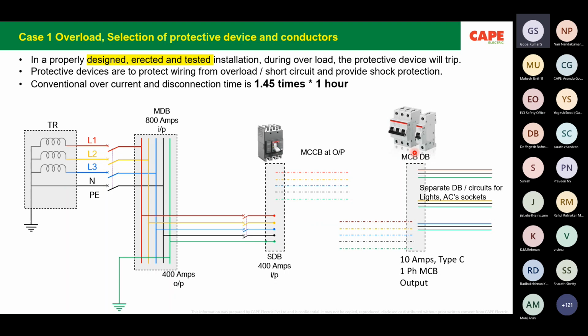In this subject, most of the time what we find is, please note that the protective devices are to protect the circuit, the wiring. Sometimes it is not to protect the equipment, it is to protect the wiring. Equipment will have its own protective device inside. This is the concept. For example, a motor doesn't have any protective device inside, so we are supposed to go for a motor starter, which has protection inbuilt. So basically, these protective devices are protecting the wiring.